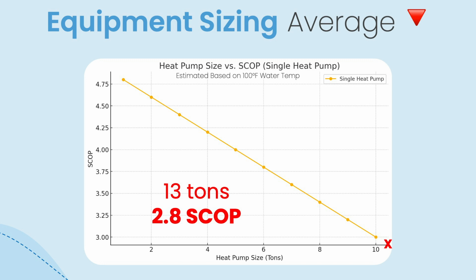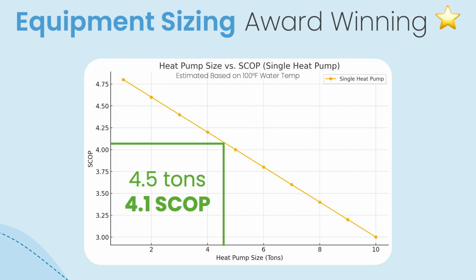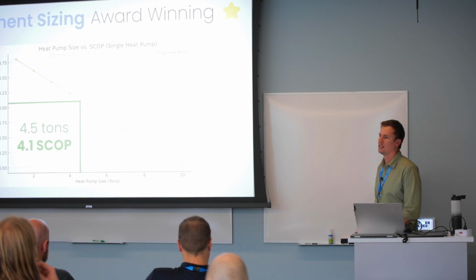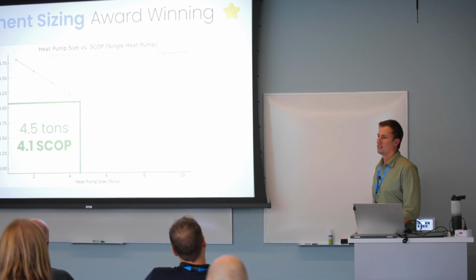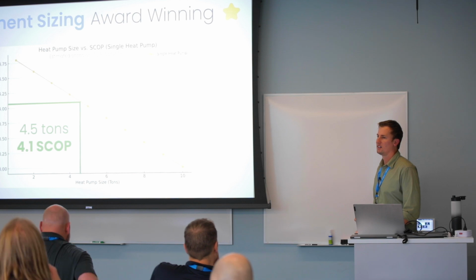Generally at this size, smaller it doesn't really make sense, but when you get to around 4 tons and definitely higher, it becomes more efficient to have what's called cascade heat pumps, which is just a fancy word for having 2 heat pumps connected together. So instead of 1 big one, 2 small ones, and they share the load between them. When it's at a small tonnage, it doesn't really matter because it's negligible differences and it's not really worth the cost. Sorry, yeah? In the cascade design, are the 2 systems serving the same square footage, or are you dividing the space? Like you just have a portion of the home served by the first heat pump and a portion of the home served by the second?